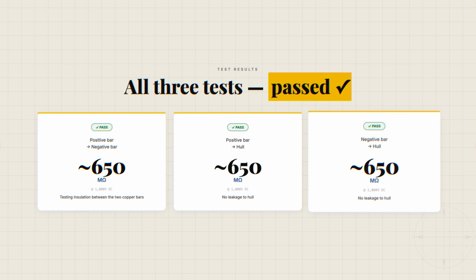All right, so I did all 3 tests. They all passed with very high readings, around 600 to 700 mega ohms depending on which one I was doing, at 1000 volts, which is a very high resistance value.